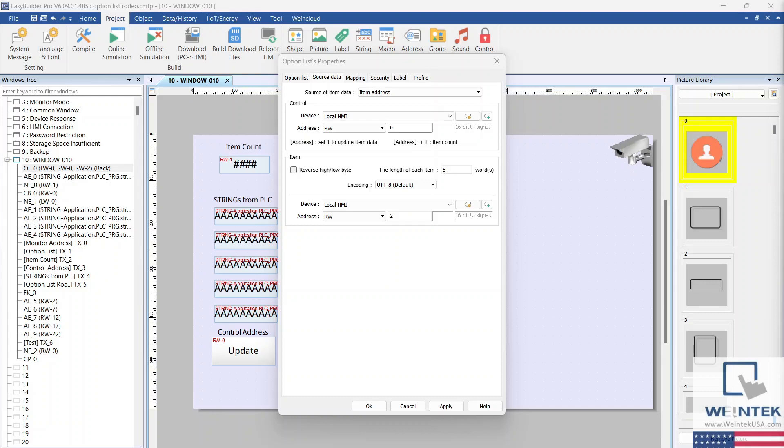RW registers are saved in HMI flash memory one minute after the HMI boots up, and then consecutively every minute after. The data within RW registers will be retained in the event of a power cycle.